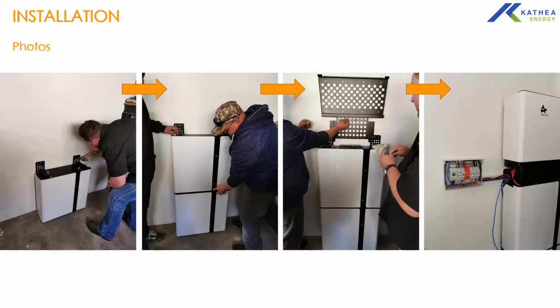And then to connect the top battery and the bottom battery, you take from the sides of the top battery to the top of the next battery, and so on if you have more than 2 batteries. So to loop your batteries for the power cables, you take from the side to the top of the next battery, and so on. And the cable lengths are enough. Let's say if you want to connect other modules on the side, the cables are long enough to get to the termination points of the next battery if it's mounted side by side.